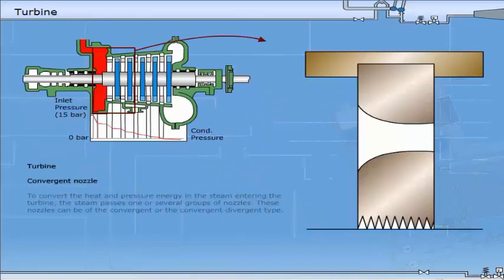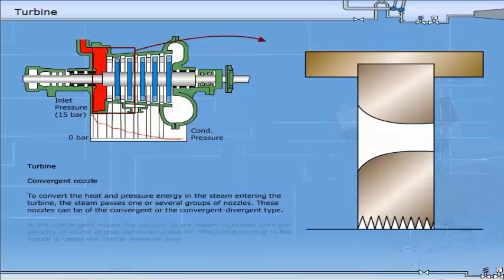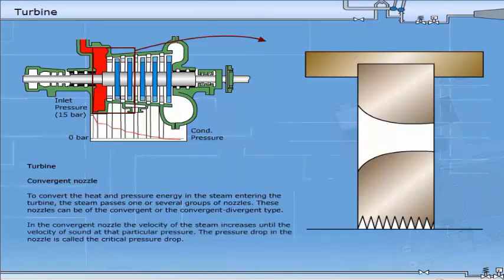To convert the heat and pressure energy in the steam entering the turbine, the steam passes one or several groups of nozzles. These nozzles can be of the convergent or the convergent-divergent type. In the convergent nozzle, the velocity of steam increases until the velocity of sound of that particular pressure.